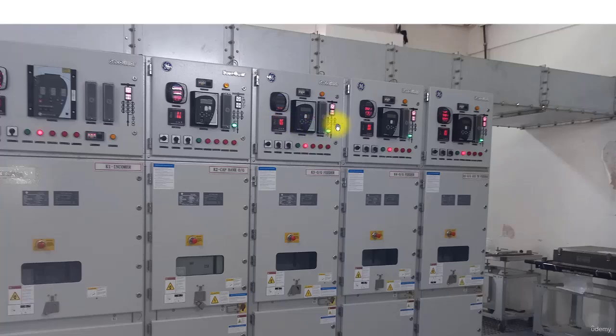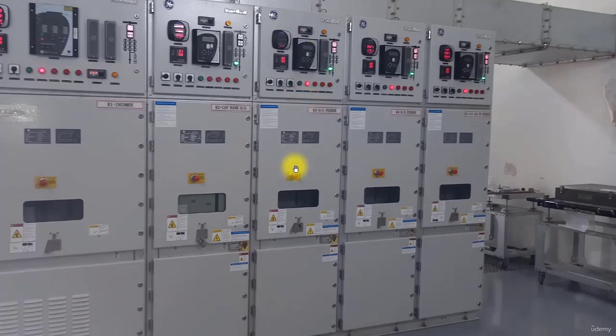Further, if you come down, you can see this is the mimic. So the mimic is also together with the protection control here, and at the top you can see this is the device that is a capacitive voltage indicator, and this device is installed to show whether the cable is live or not live. So if the cable is live, the LEDs will blink on and off here, and the operator will know whether the cable is energized or not energized. Downside, you can see there are switches which are there to issue the closing and tripping commands, and these are the indications. So we can see this is basically a switchgear, which is a combination of the breaker, and you can open this door and you can rack out and rack in the breaker as well.